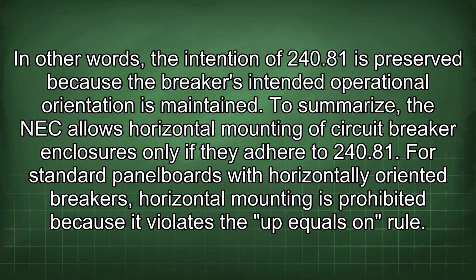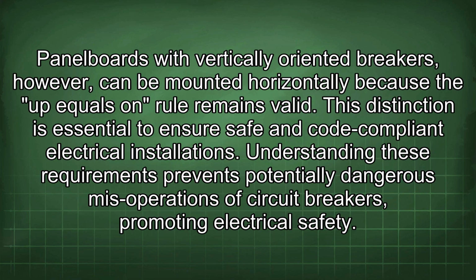To summarize, the NEC allows horizontal mounting of circuit breaker enclosures only if they adhere to 240.81. For standard panel boards with horizontally oriented breakers, horizontal mounting is prohibited because it violates the up equals on rule. Panel boards with vertically oriented breakers, however, can be mounted horizontally because the up equals on rule remains valid. This distinction is essential to ensure safe and code-compliant electrical installations. Understanding these requirements prevents potentially dangerous misoperations of circuit breakers, promoting electrical safety.